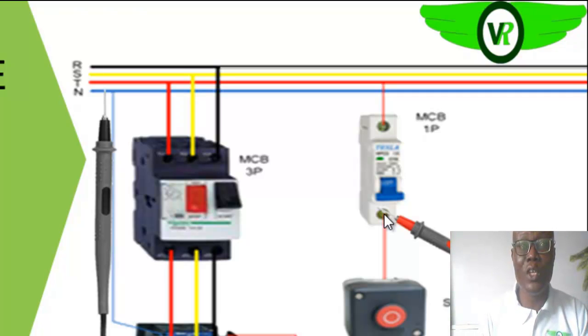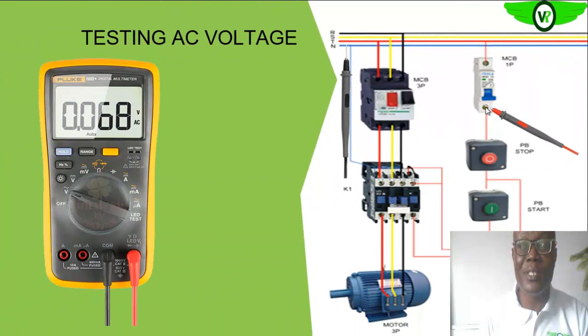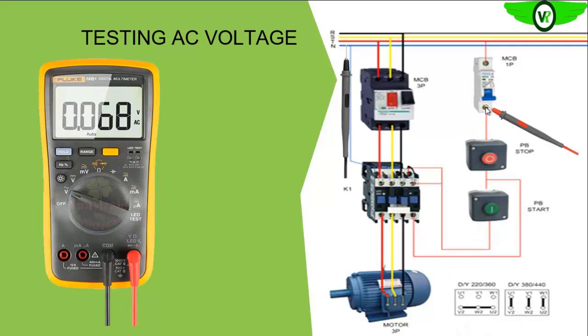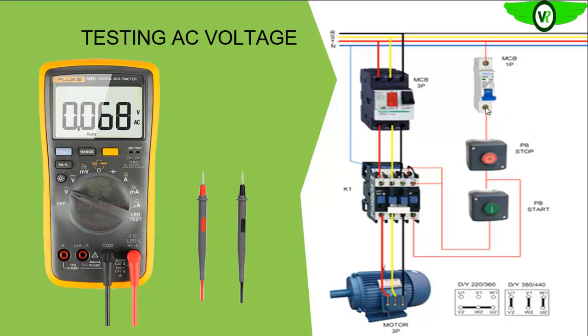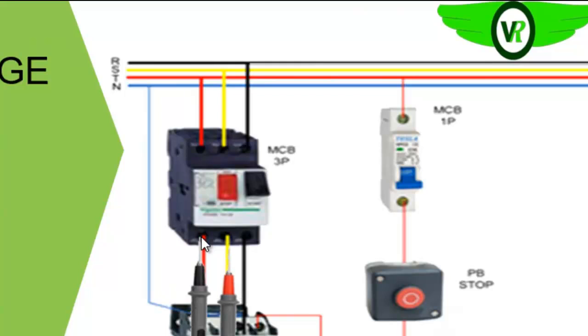When you put it off, what you have will be 0 volts. When you put it on, what you have should be 220 volts. So if you are not having that, it means that that circuit breaker is faulty. Remember, what we are doing is testing the AC circuit. Okay, so let's assume that the output from that circuit breaker is fine. Okay, now the next test that you want to do will be phase to phase. So you take the black probe to the other phase, and then the red probe to line 1.